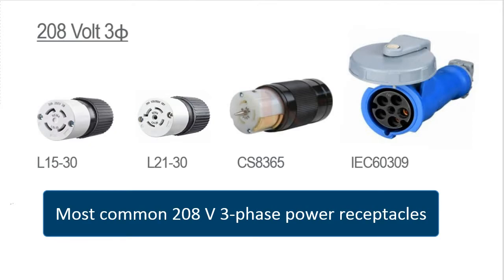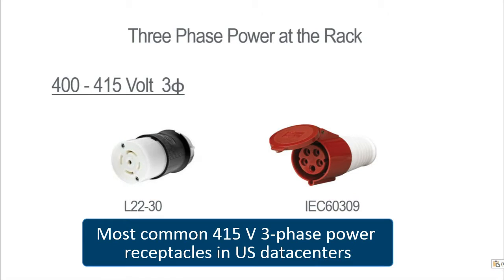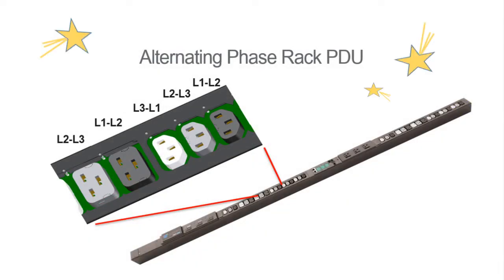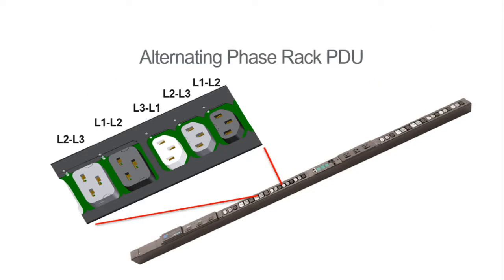Take a look at the most common 208-volt three-phase power receptacles that you'll find in data centers — you're probably familiar with them. And these are the most common 415-volt three-phase power receptacles you'll find in U.S. data centers. Now let's move to the PDUs. This illustration shows that a conventional three-phase rack PDU has its outlets grouped by phase, or phase pair, in three to six distinct locations along the length of the PDU. In contrast, meet the star of this video: an alternating-phase rack PDU, where the phase of the outlets alternates every outlet.